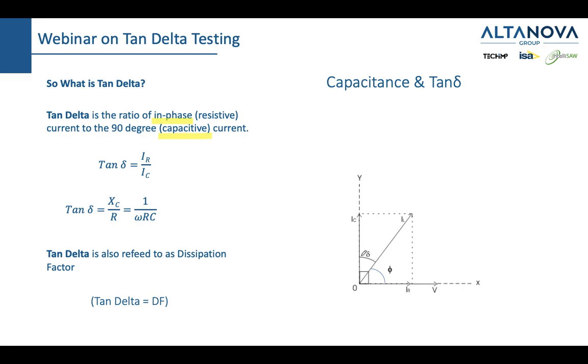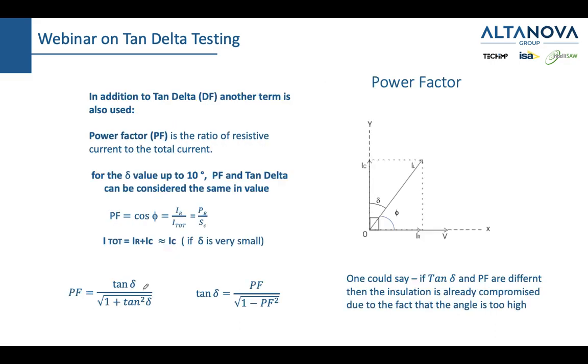Another name for tan delta is dissipation factor. And dissipation factor has been used in some other countries. So let's say in some countries they say, I'm measuring C and DF instead of I'm measuring tan delta. And then there are some countries like USA, which use the term power factor. Now, actually, tan delta and power factor are very, very similar.